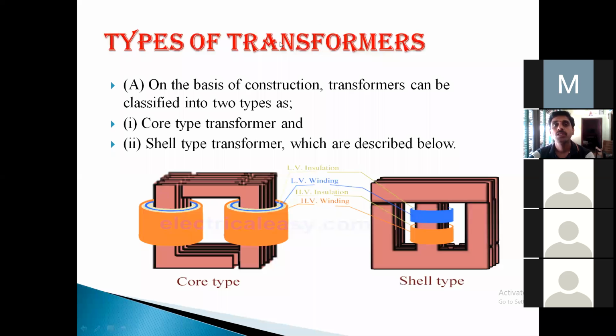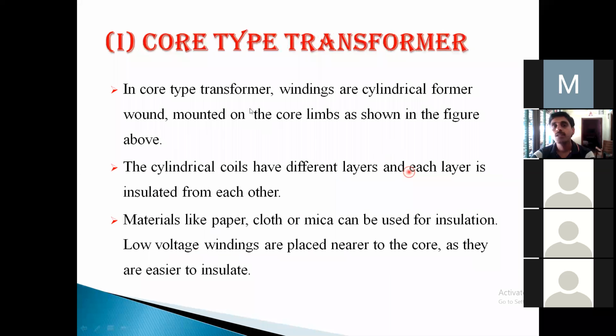I've seen this. So what are the types of transformers? On the basis of construction, they are classified into two types, that is core type and shell type transformer. Have you come across core type and shell type? So this is core type. Core type means the winding surrounds the core. So this is the core, and the winding is on both the sides. This is shell type. That means the winding is internal to this and the core is outside. In core type transformers, windings are cylindrical, mounted on the core limbs.